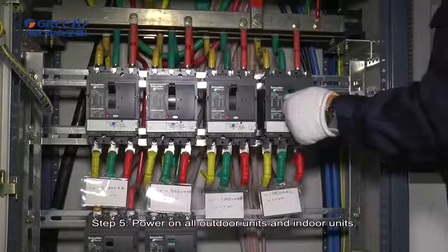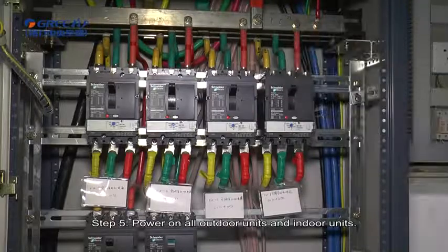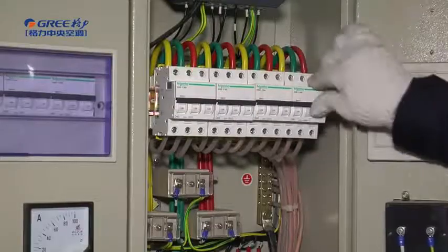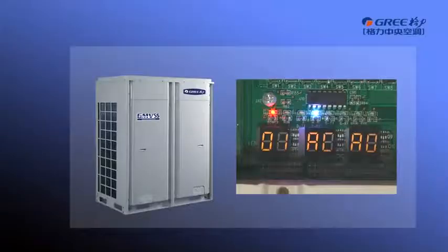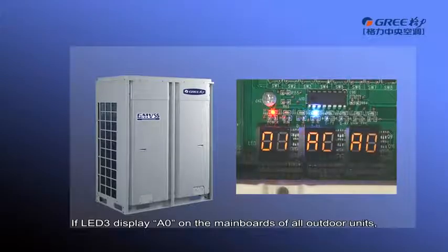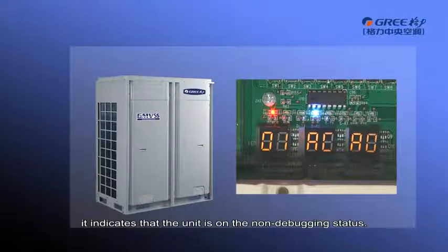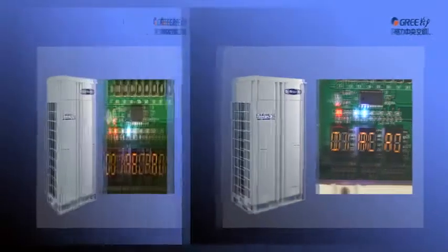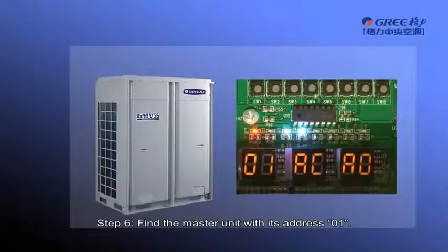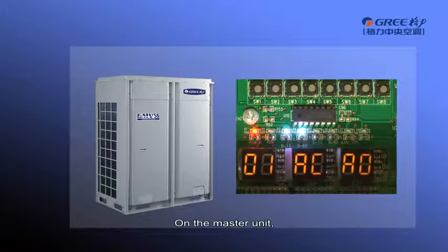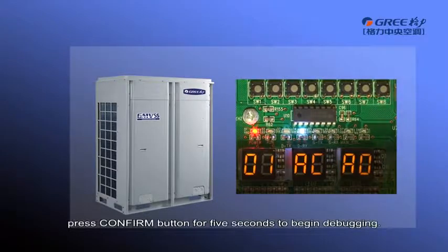Step 5. Power on all outdoor units and indoor units. If LED 3 displays A0 on the mainboard of all outdoor units, it indicates that the unit is on the non-debugging status. Step 6. Find the master unit with its address 01. On the master unit, press Confirm button for 5 seconds to begin debugging.